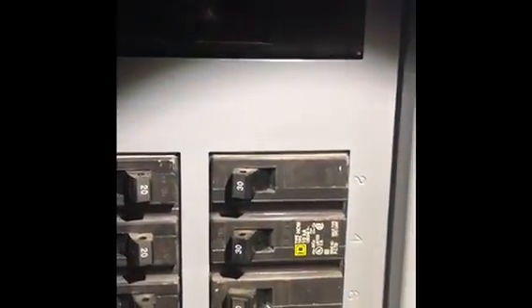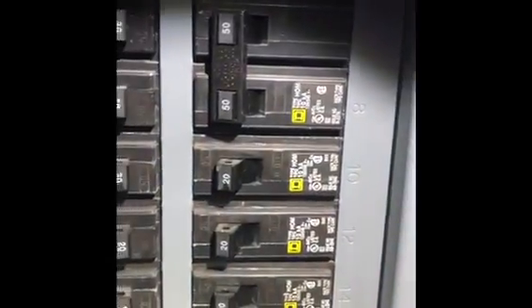The panel looks like it's been upgraded to a 200-amp panel. The air conditioner is one of the top two breakers, from what the panel box says. The furnace is number 12 — a 20-amp breaker. And this is a Square D panel box, that should be it.